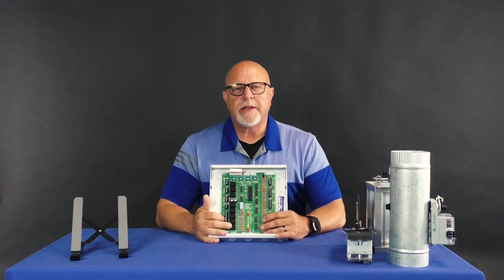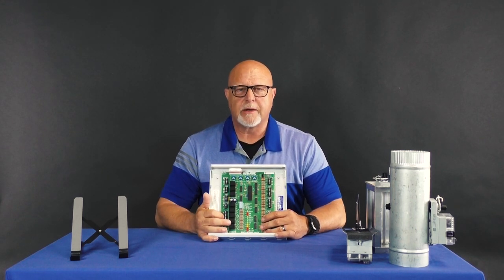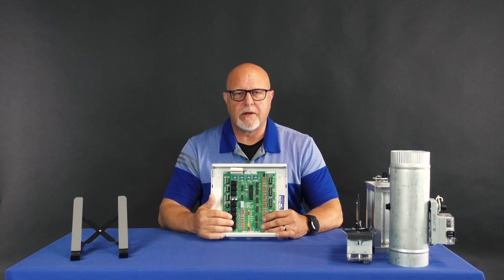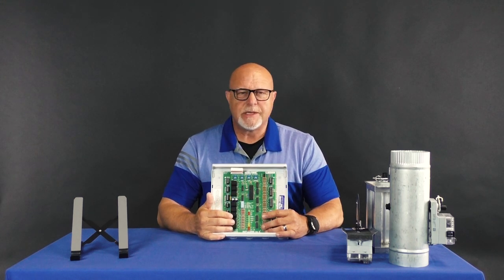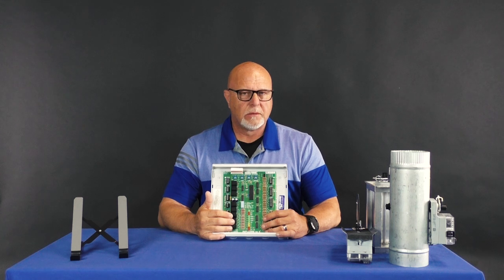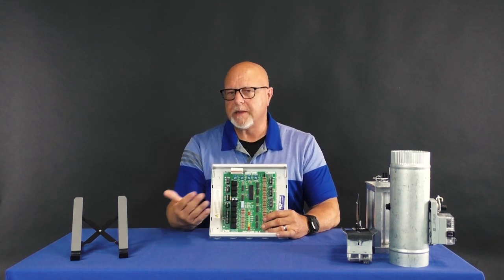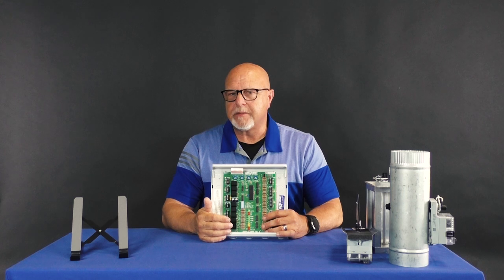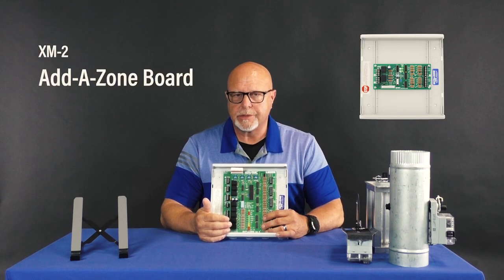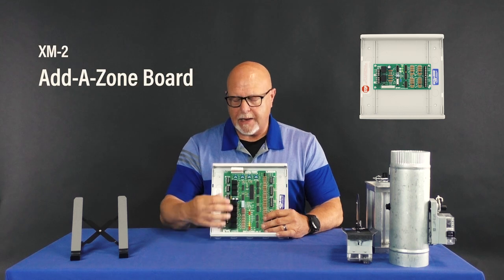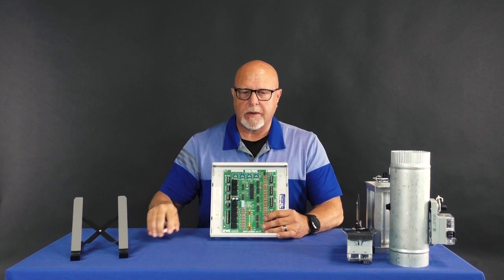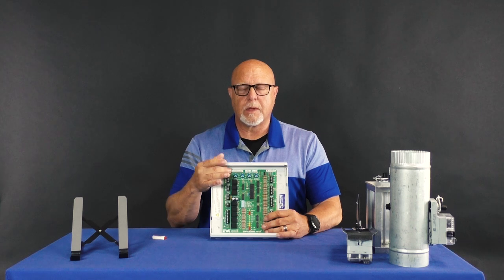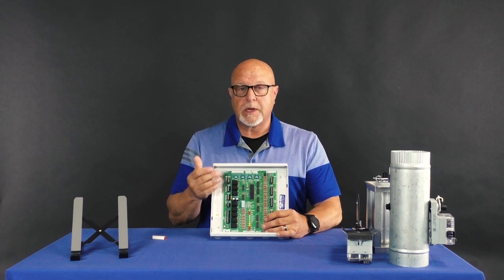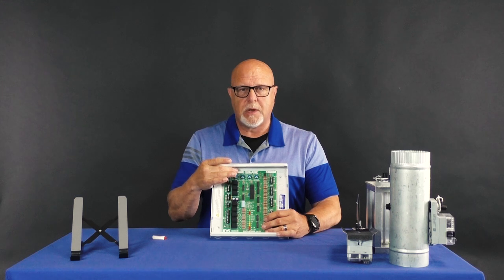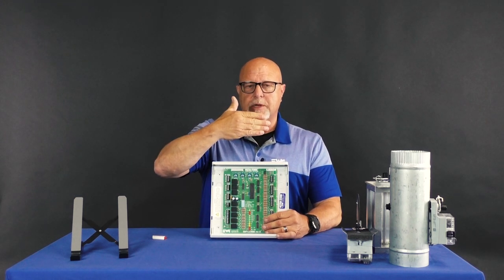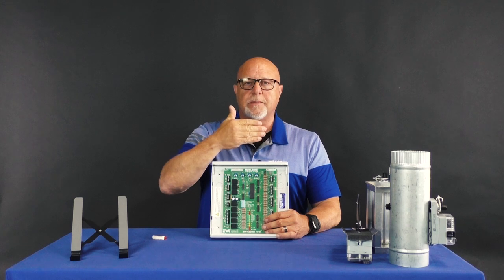However, in the event that the homeowner calls you, the contractor, and says that they want to add on to the already existing zone system, instead of having to buy a whole brand new panel, say a BM Plus 5000 or a BM Plus 7000, you would only have to buy an add-a-zone board, which is part number XM2, and that would be installed at this bus cable. The add-a-zone board would come with that bus cable or ribbon strip, and it would plug into here, and it would be mounted somewhere in a fashion above this original BM Plus 3000.